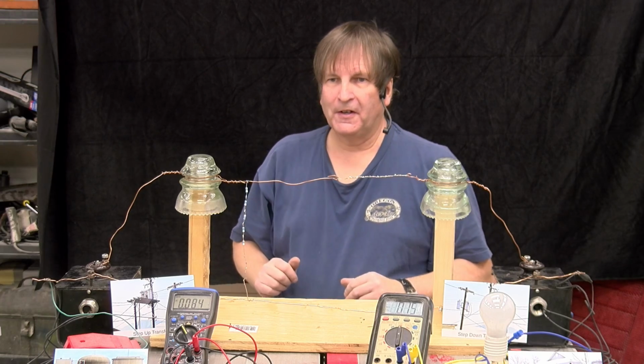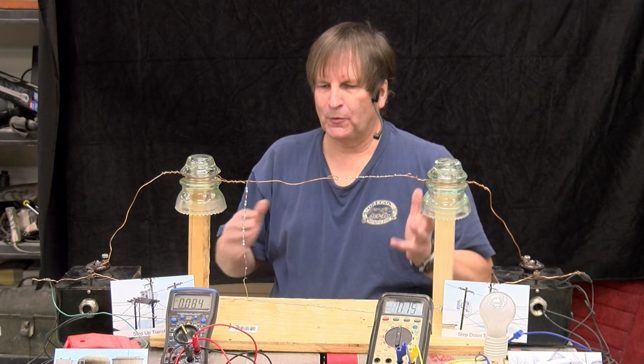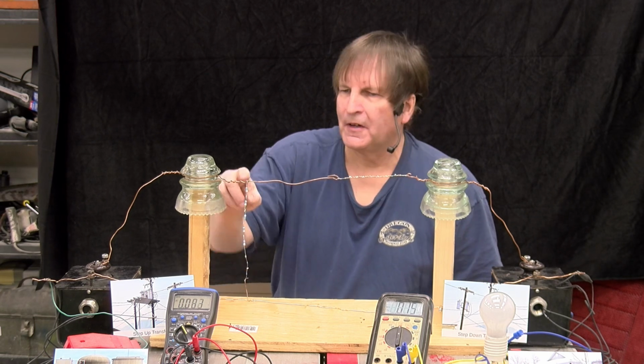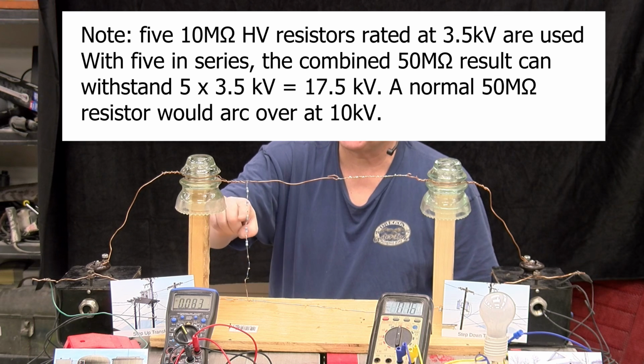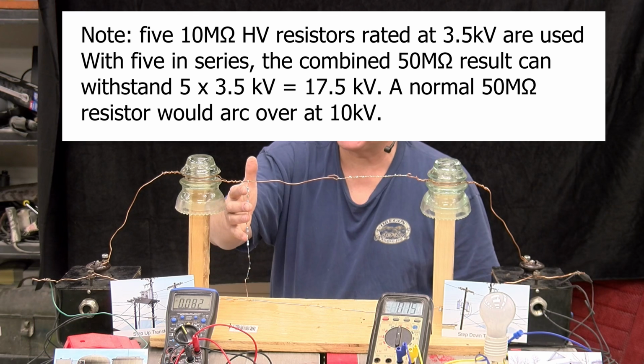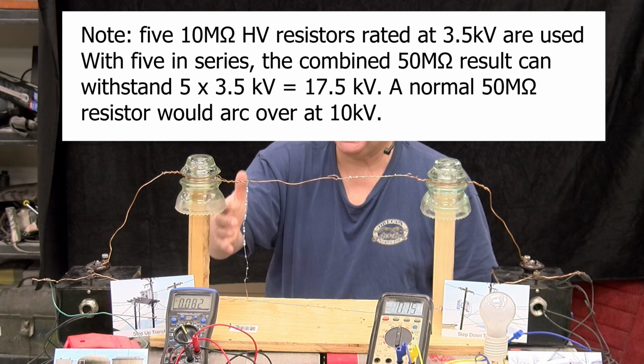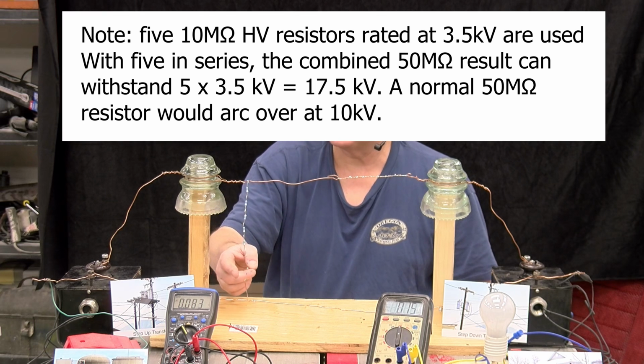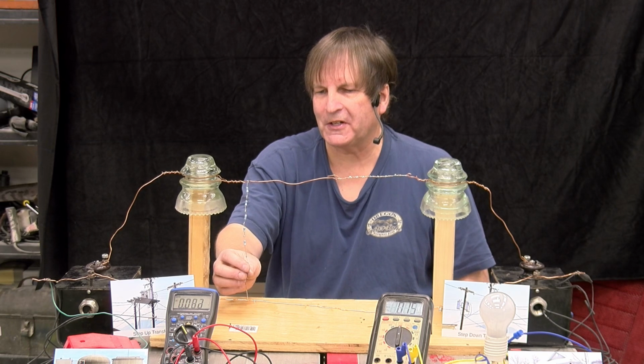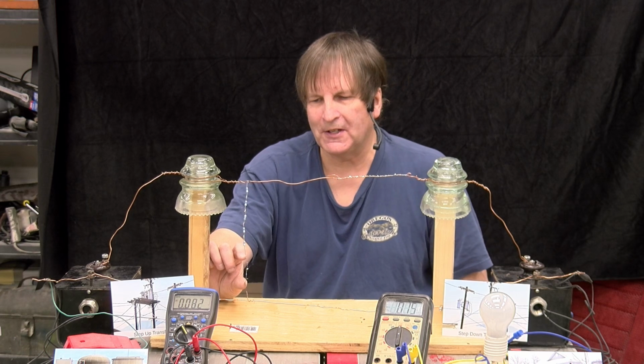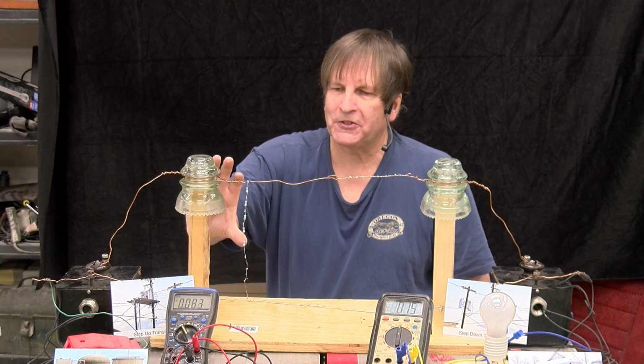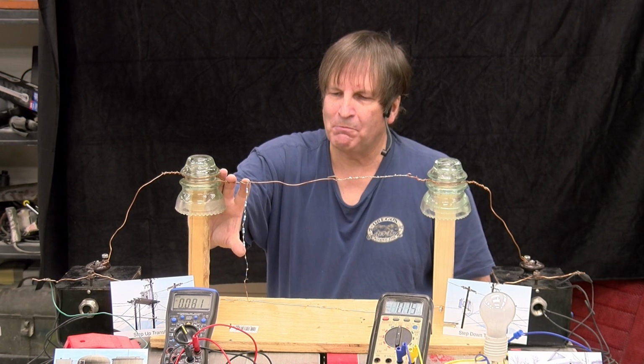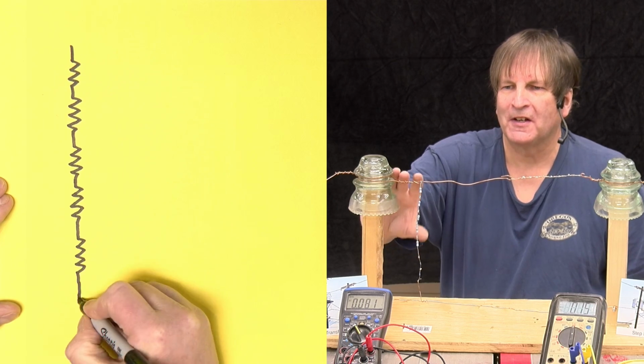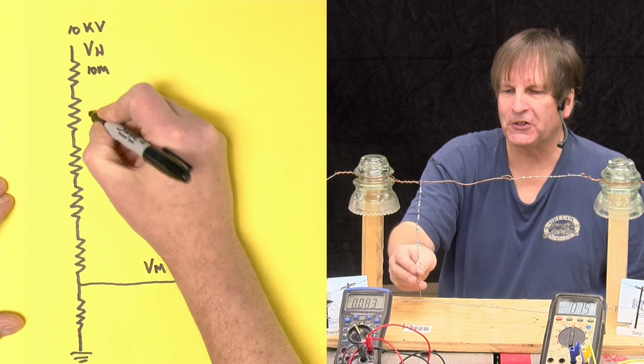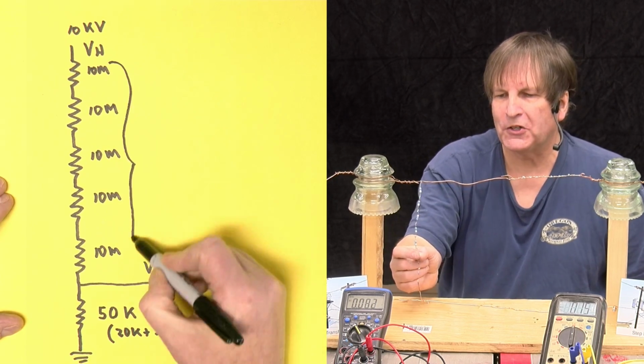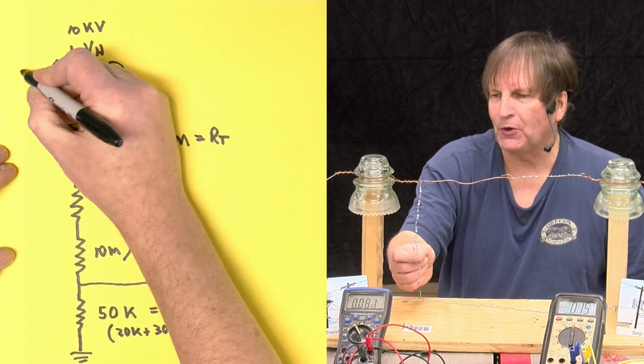So what is this resistive divider? Well, it is 50 mega ohms. I have 1, 2, 3, 4, 5, 10 mega ohm resistors in series over here, and I have a 20 and 30 kilo ohm resistor in series down here, so that the resistance between these 2 points is 50 kilo ohms. The resistance between these 2 points is 50 mega ohms. What that does is it does a 1,000 to 1 voltage division. So when this is 10 kilovolts, we should see about 10 volts at this point over here.